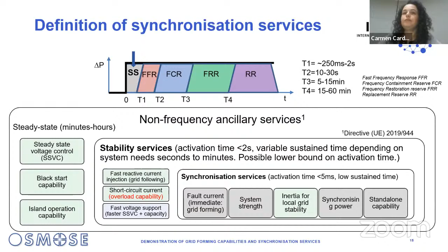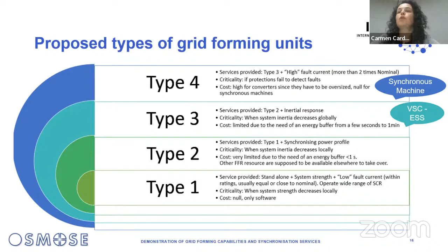So based on this definition, if we want to apply it to specific technologies like a wind farm, a storage system, a synchronous machine, or even a PV plant, they have different natures regarding the DC side energy that they dispose of. So to cope with this difficulty, we can define types of grid forming units. Basically, a type 1 grid forming unit has really low energy requirements, and we can go up like that. A type 3 grid forming unit, for instance, is what we are doing today. It's an energy storage system that can provide inertial response and synchronizing power, but not necessarily classical frequency regulation. This is an option, and it will be decided by the operator of the system, the battery system, I mean. And of course, to avoid any doubt, a type 4 grid forming unit is a synchronous machine, and the specificity is that it can also provide high fault current. For the other types, the fault current is limited to the rating of the converter.